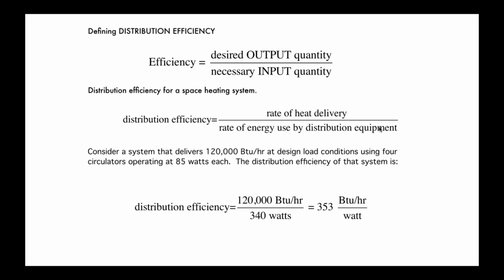And we get this number over here, 353 BTUs per hour per watt. You're probably looking at that and scratching your head saying, well, what does that mean? Well, it means for each single watt of electrical power to operate this particular distribution system, it's delivering 353 BTUs from where the heat was produced to where it's needed in the building.